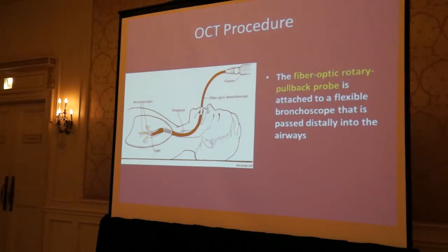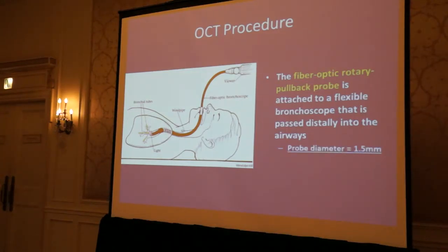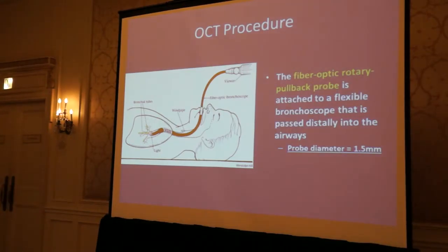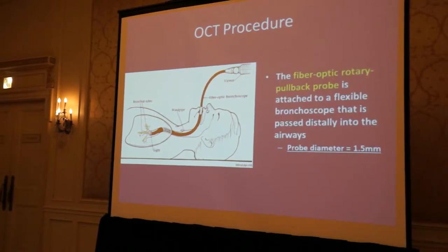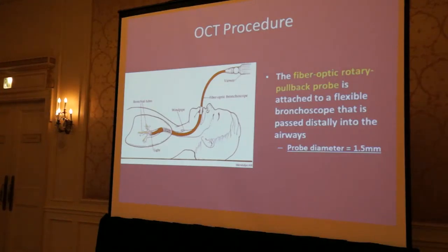Once the bronchoscope reaches the opening of the desired small airway, a probe continues to move throughout the smaller airways blindly — the doctors cannot see which branch it is moving into. Because the probe has a 1.5-millimeter diameter, it will continue into the small airway until its diameter equals that of the airway, at which point a 5-centimeter pullback occurs. During this pullback, continuous images are taken so that post-investigation 3D airway reconstruction is generated.